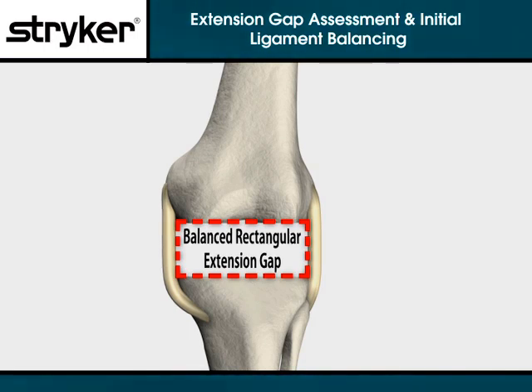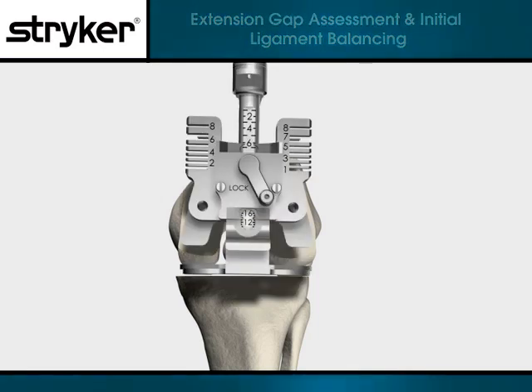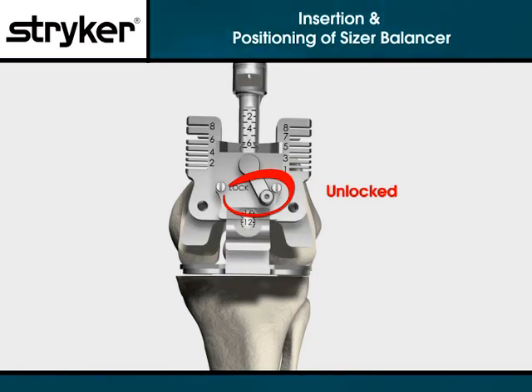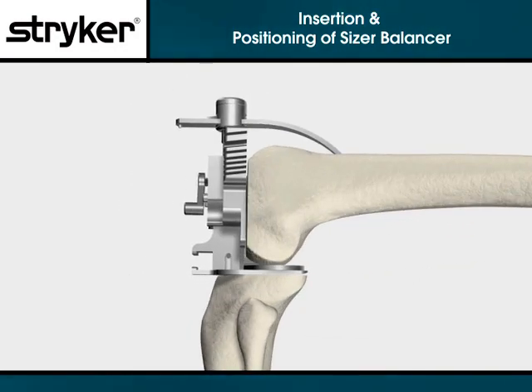After the extension gap is balanced and rectangular, measure the gap in millimeters that equates to a Triathlon insert. Remove the spacer block and bring the leg into 90 degrees of flexion. Be sure that the sizer balancer's lock lever is set to the right, or unlocked, position. Insert the sizer balancer, placing the feet between the tibial surface and the uncut posterior condyles.